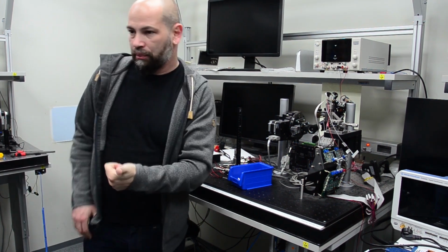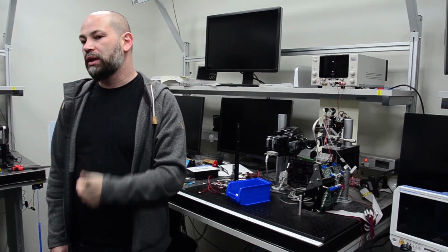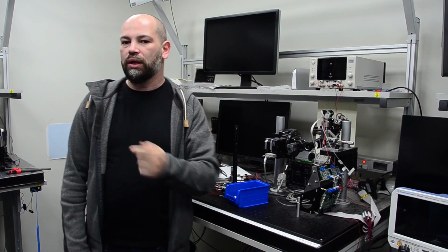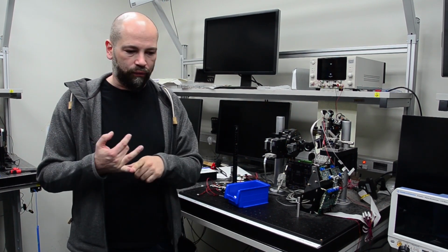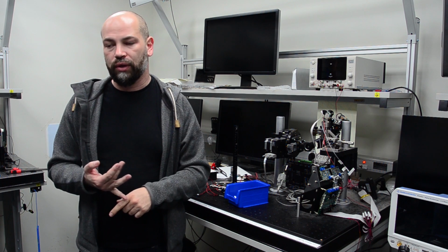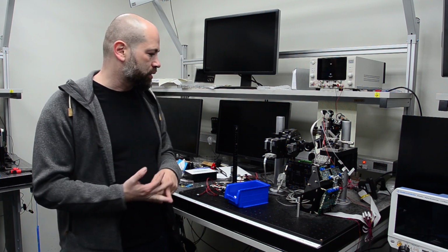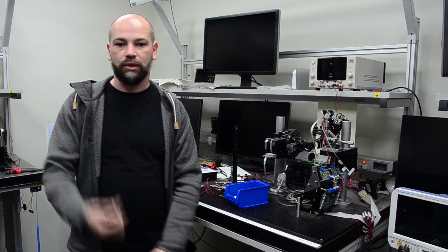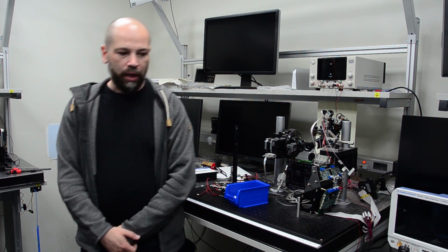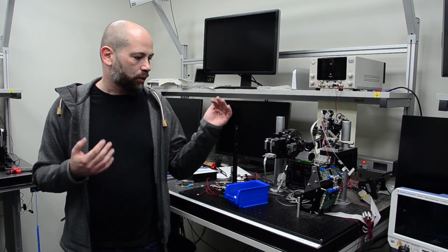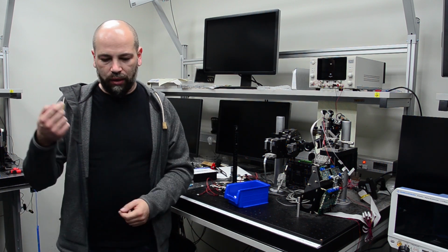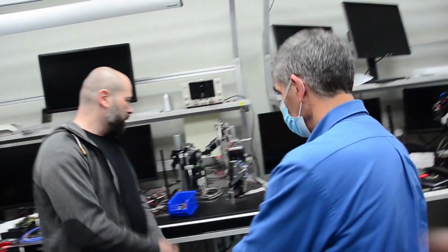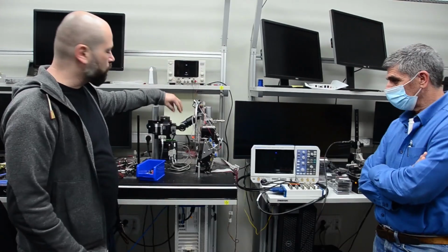It is sampling the eye position 20,000 times a second, significantly more than any camera. It's measuring the optical axis of the eye, so it's independent of the relative position and imperfection of the eye itself. It is not dependent on the shape of the external part of the eye, since we measure the internal part of the eye. And it is a modulated signal, therefore we are completely insensitive to the ambient illumination conditions. So what you see here is basically we follow the eye.